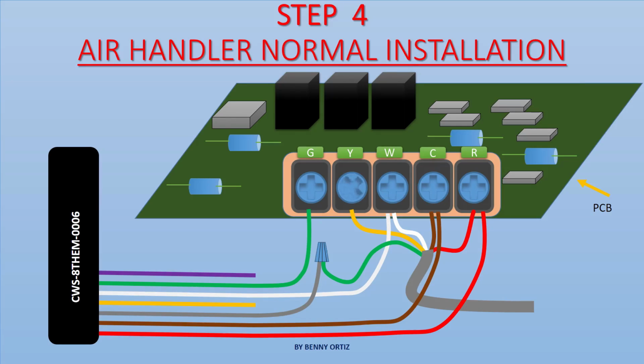Remove the yellow wire from the Y terminal and release it from the Y terminal. Wire nut the HVAC chip yellow wire to the yellow wire released from the Y terminal. Then connect the purple wire from the HVAC chip to the Y terminal of the air handler unit. Tighten down the screws. Check to make sure all the wires are secured.